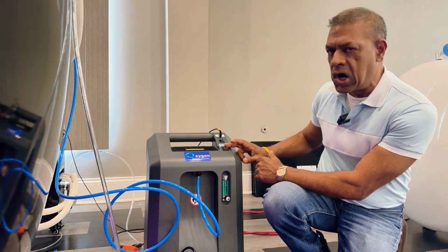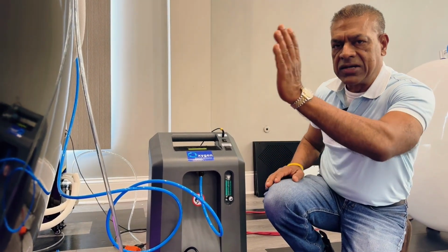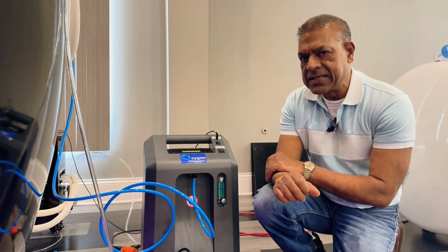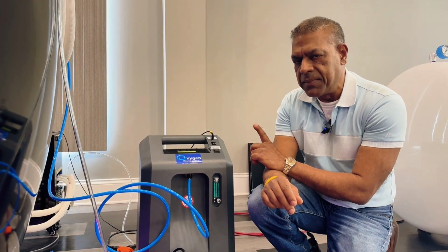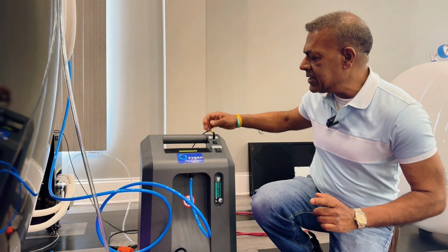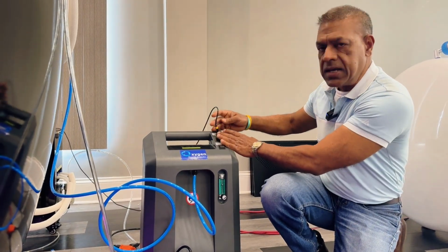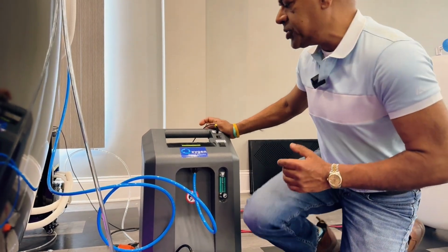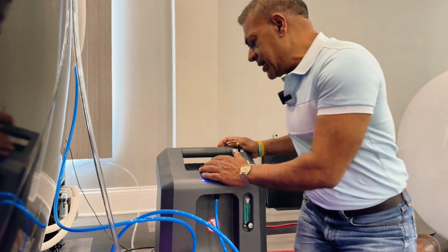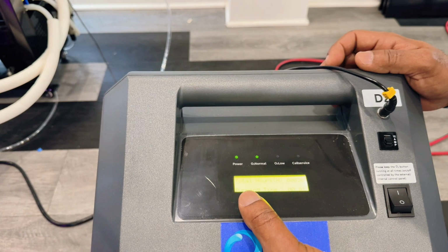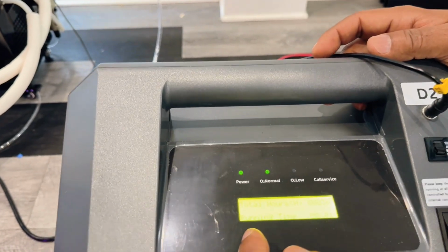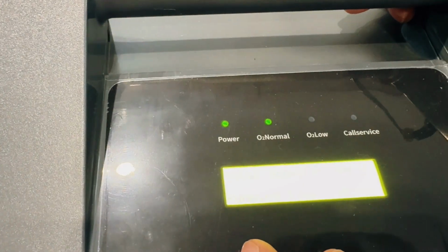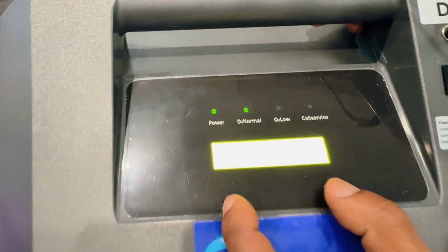It is very easy to operate. You turn it on and leave it on, and then once you select the pressure or pressurization process, the oxygen concentrator would come in automatically by means of these 2 wires, D1 and D2. The display panel will show you the number of operations. The operation here is 36 hours, and runtime is for the last 2 minutes.